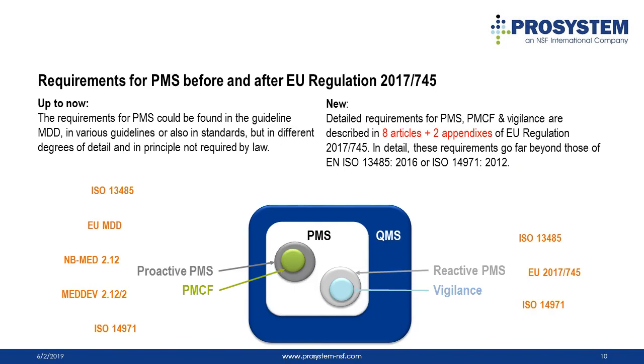As I already mentioned before, the requirement to have a PMS system is not new. EU MDD, NBMED 2.12 and MEDDEV 2.12/2 have all had elements of PMS activities, which were now merged into the MDR. Detailed requirements for PMS, PMCF, and Vigilance are described in 8 articles and 2 annexes of the EU regulation.